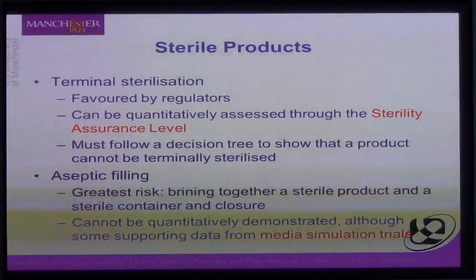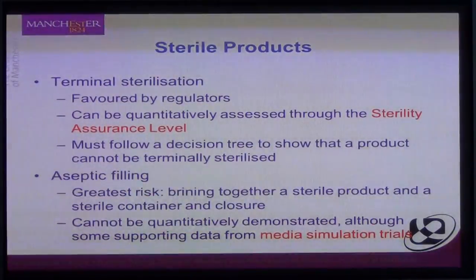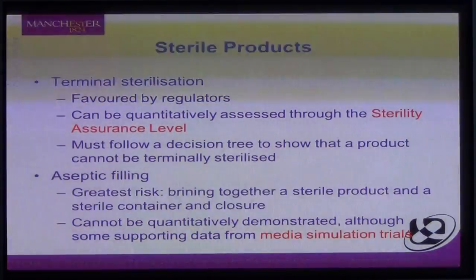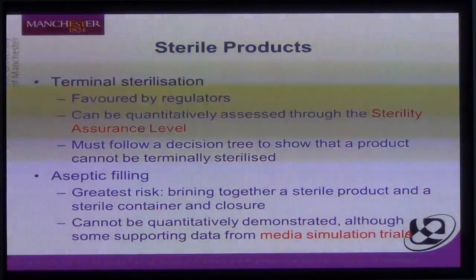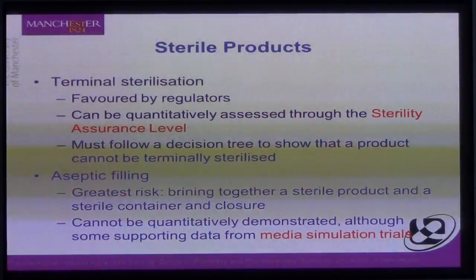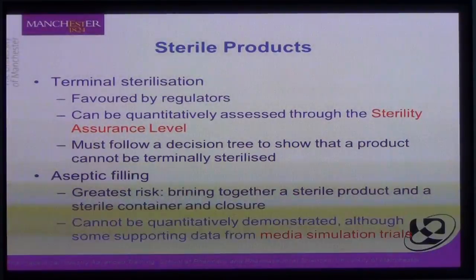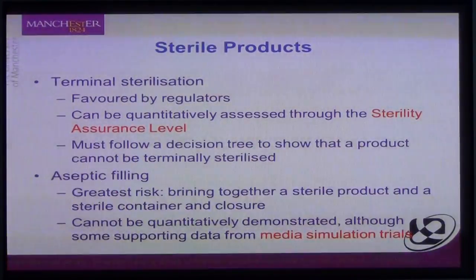In aseptic filling, you bring together a sterile product sterilised by filtration, sterile containers passed through a depyrogenation oven, and a sterile rubber closure, then you put them all together trying to maintain sterility. This cannot be quantitatively demonstrated — there is no probability or formula to say that an aseptically filled product is sterile. All we can do is ensure good environmental control and regularly practise aseptic filling through media trials.